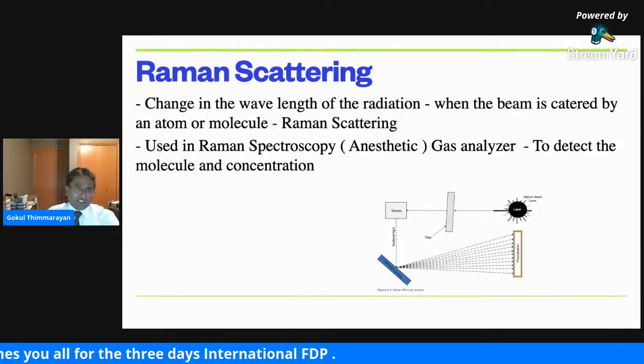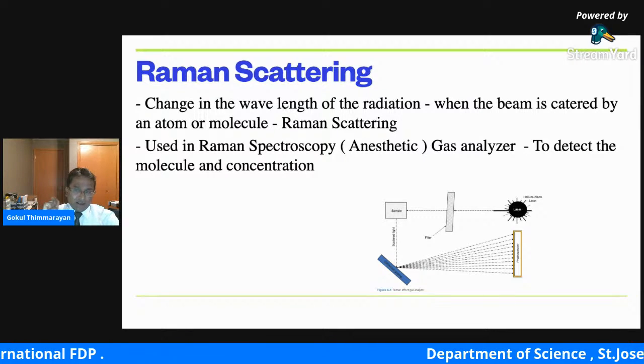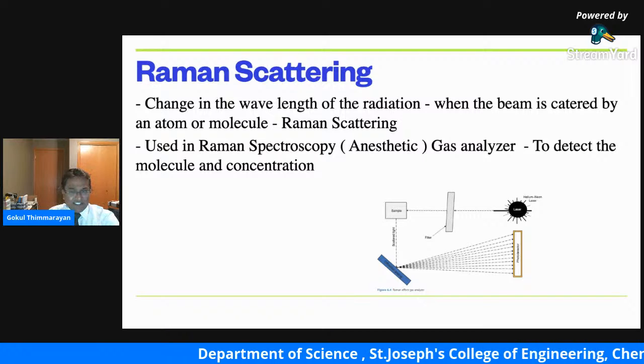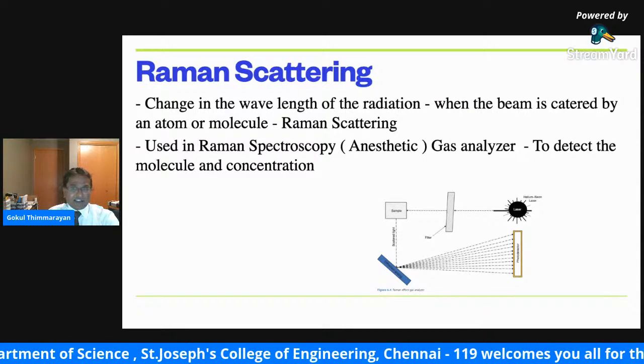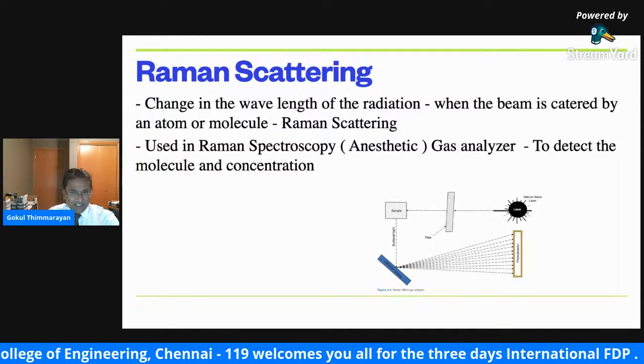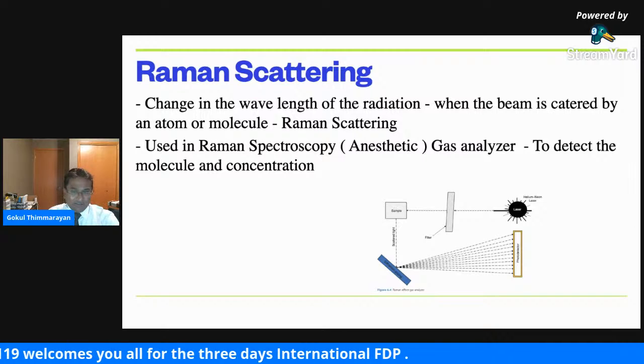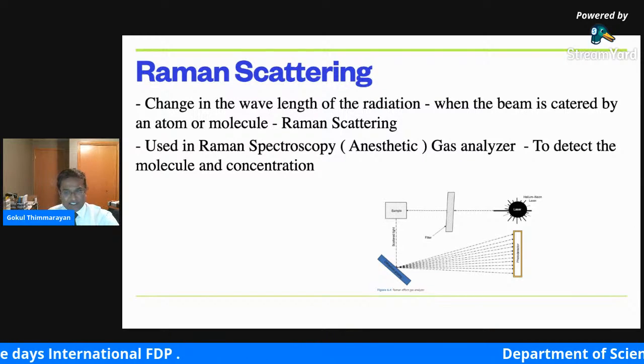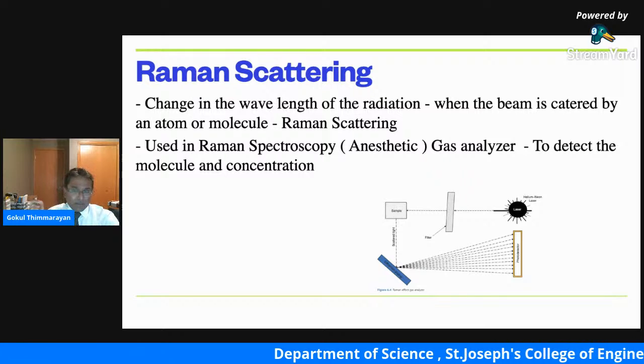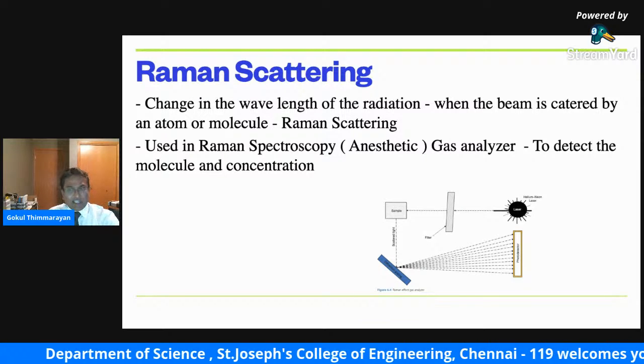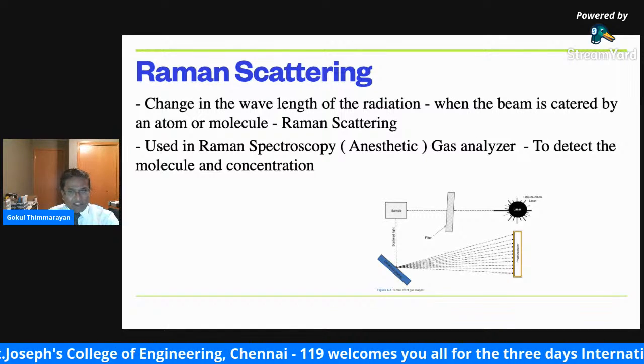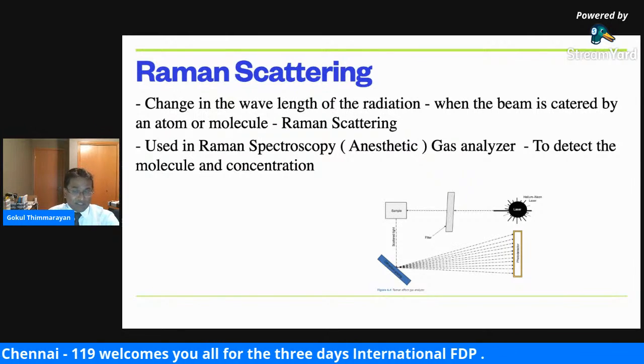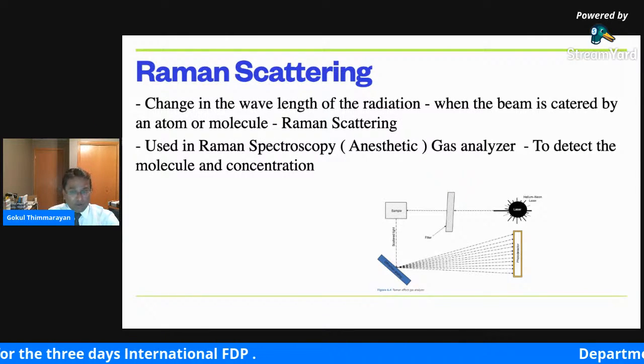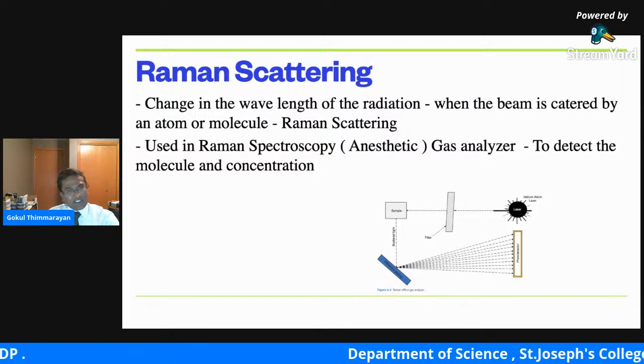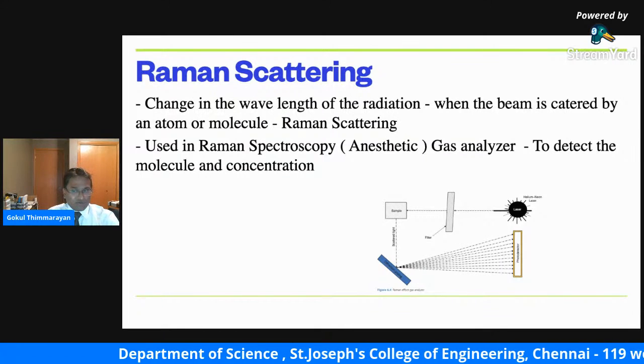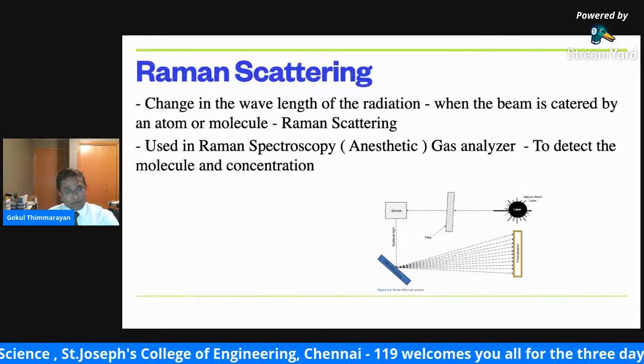And the other method is Raman scattering. So a laser beam is passed through the sample, and when it hits the sample gas, there's a change in the wavelength of the laser light. After it passes through the sample, it hits the diffraction grating, and after it gets diffracted, it's detected in the sensor. So based on the nature of the molecule present in the sample, there's a change in the wavelength of the laser light. With that, we could identify which gas molecule is present that we intend to analyze. And also based on the amount of scattering, it gives us the concentration of the gas. And this is the Raman scattering principle used in identifying the sample, which gas and its concentration that we intend to analyze.